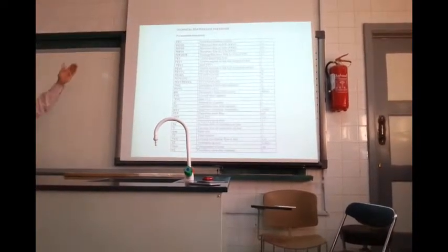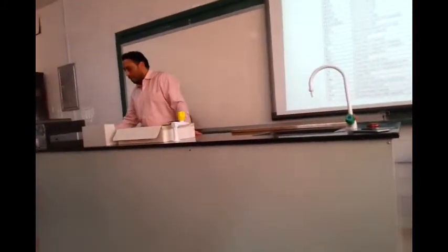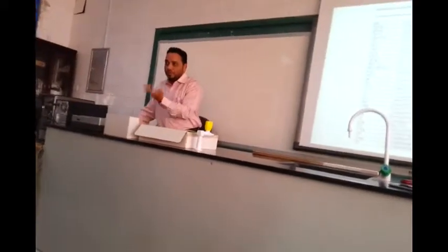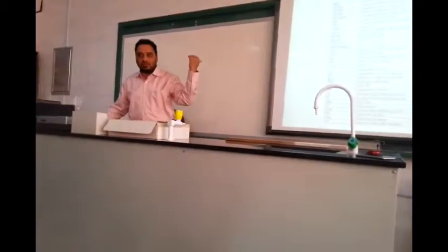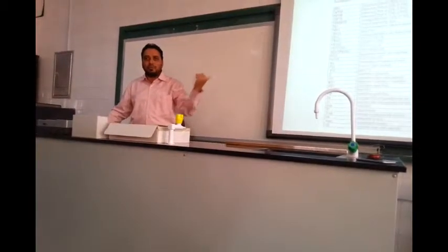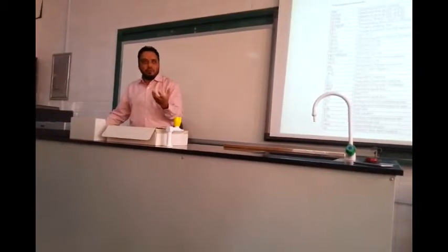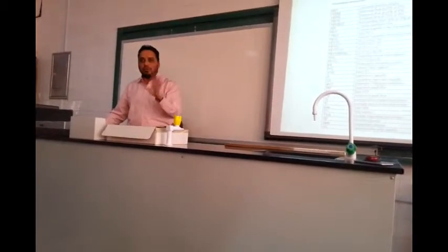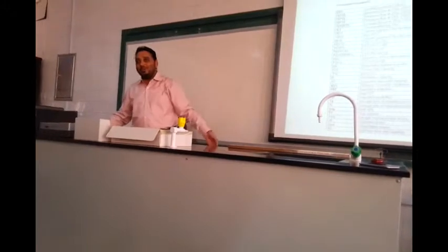Like I have told you, there are many parameters which are measured using the spirometer. Particularly because we have the electronic one, it can calculate many things using algorithms. Not like the water spirometer, which was very primitive and could calculate only the vital capacity and the inspiratory and expiratory volumes. This one is doing all these things.